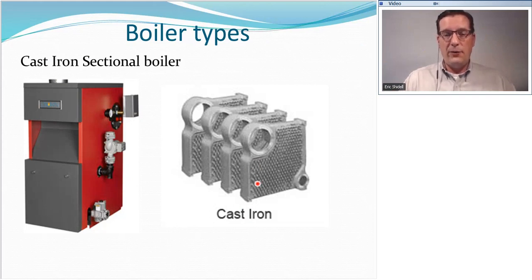It will flow through the hollow section and exit on the other side. Meanwhile, the flame would be burning underneath, and the hot gases, the products of combustion, the flue gases, are going to be circulating up along the outside of this heat exchanger or boiler section.